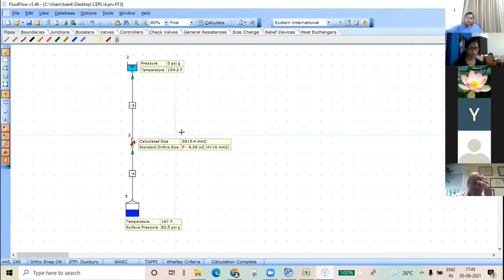True. And if you remember example 1, we are also getting P orifice, right? So it is also giving the same number. I checked in HYSYS the temperature drop. Okay, it is more or less matching. So we can trust this temperature out. So this was example 1, right? This was for critical flow, if you remember.